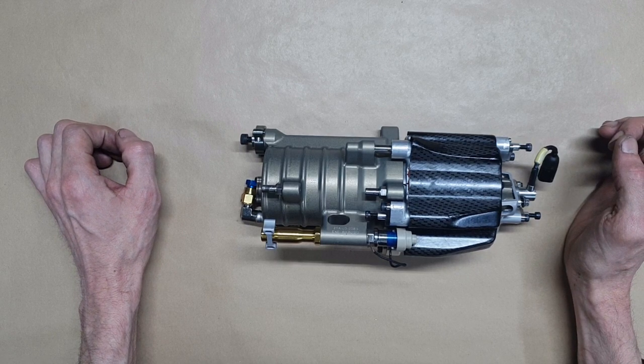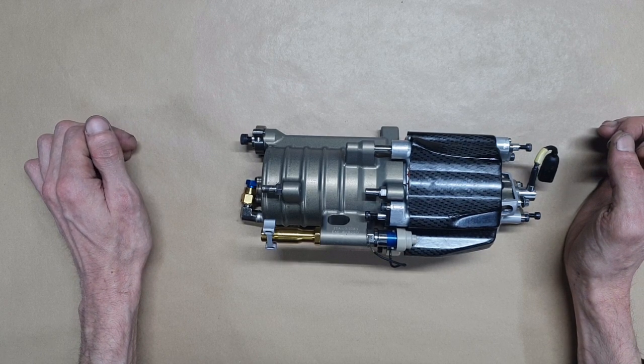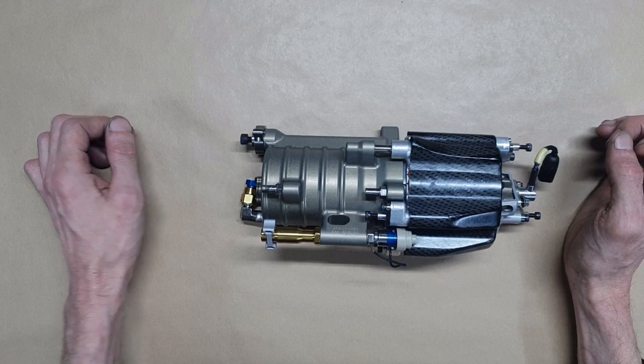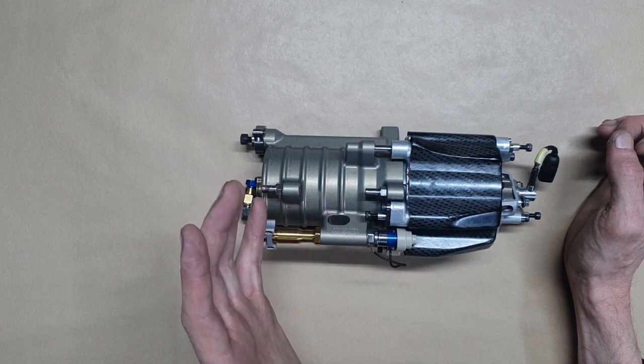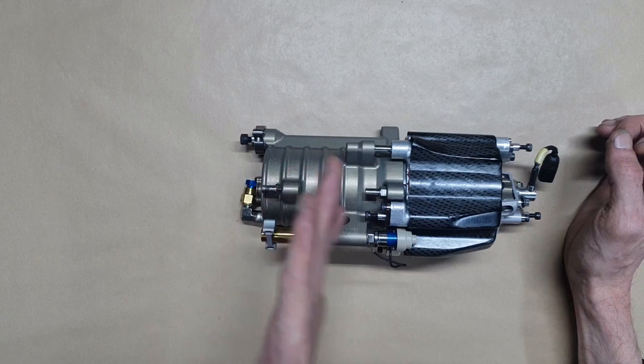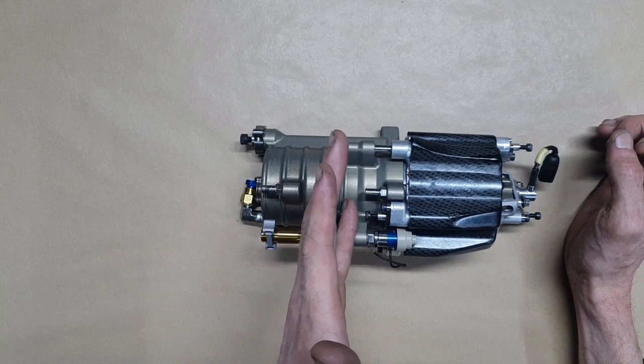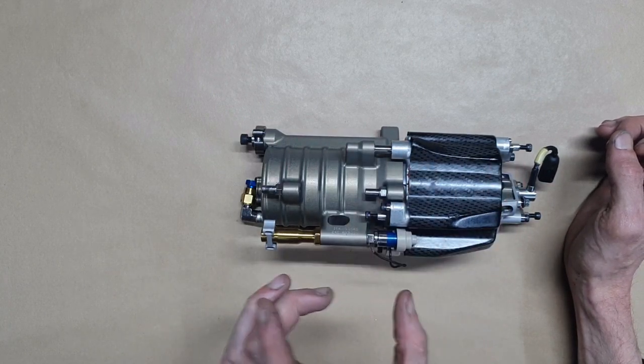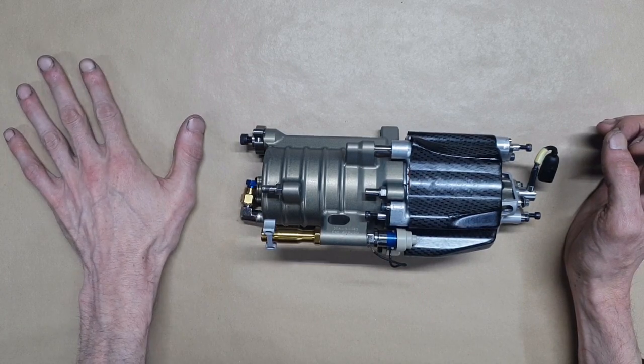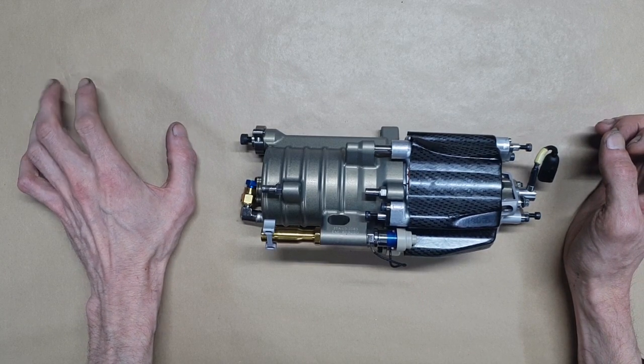Now, in terms of response rate, the diaphragm type accumulator will have a better response rate because the inertia of the diaphragm is so low, whereas this is quite a big piston with a shaft on it, so it takes longer to react.